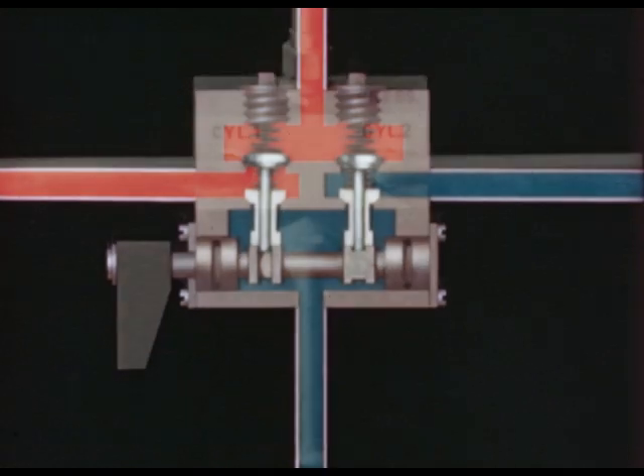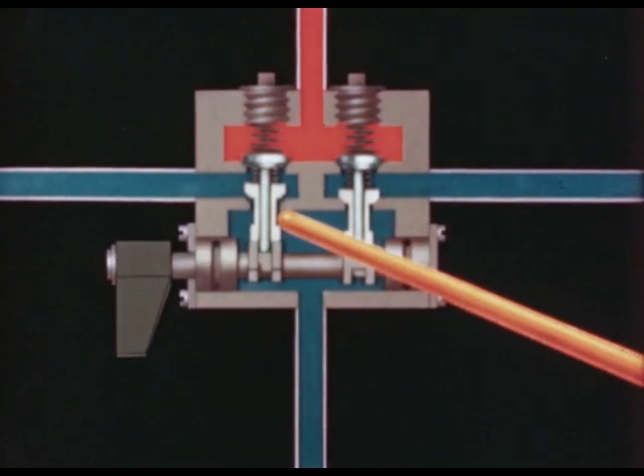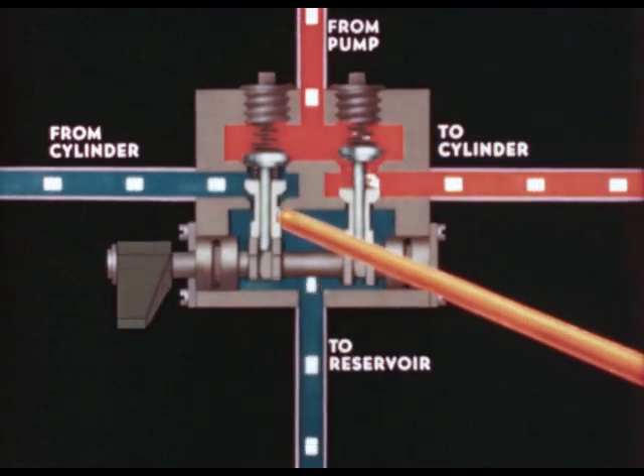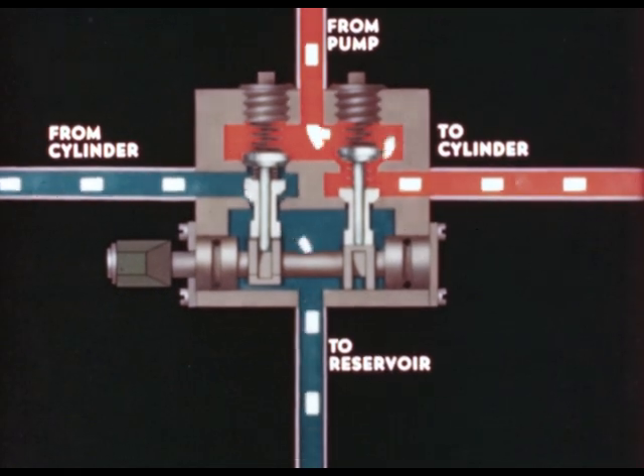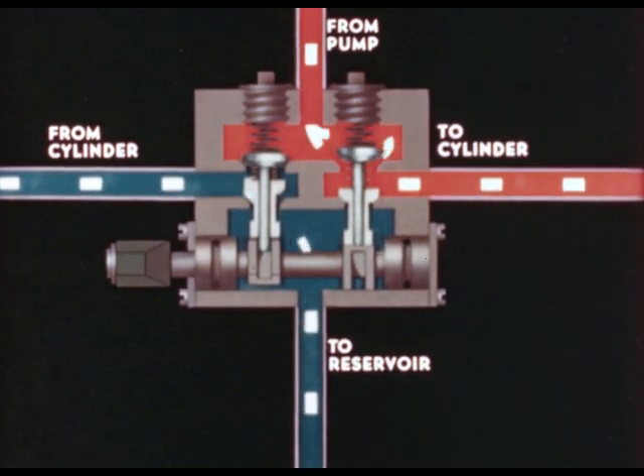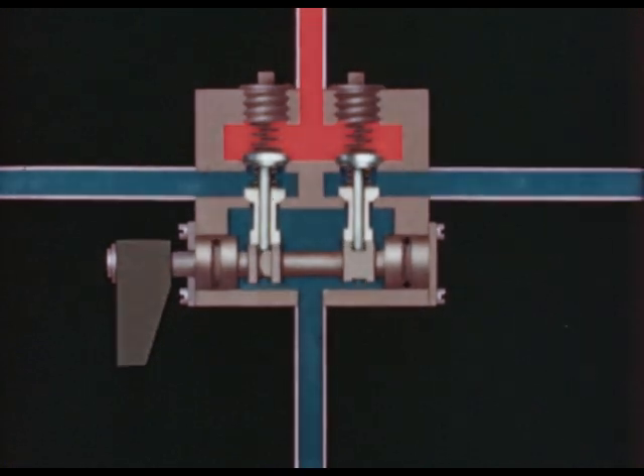Moving the handle of the valve one way first opens the return poppet from one end of the cylinder and then opens the pressure poppet to the other end. Moving the handle the other way reverses the order and causes the piston to move in the opposite direction.